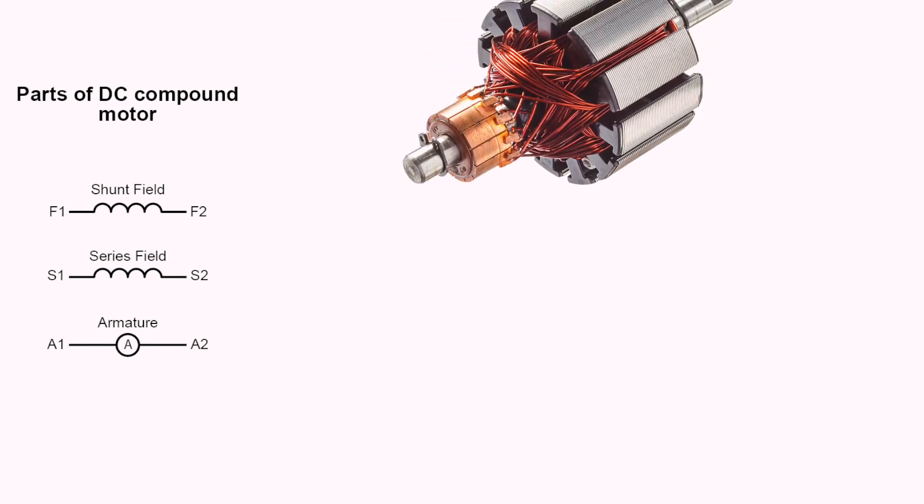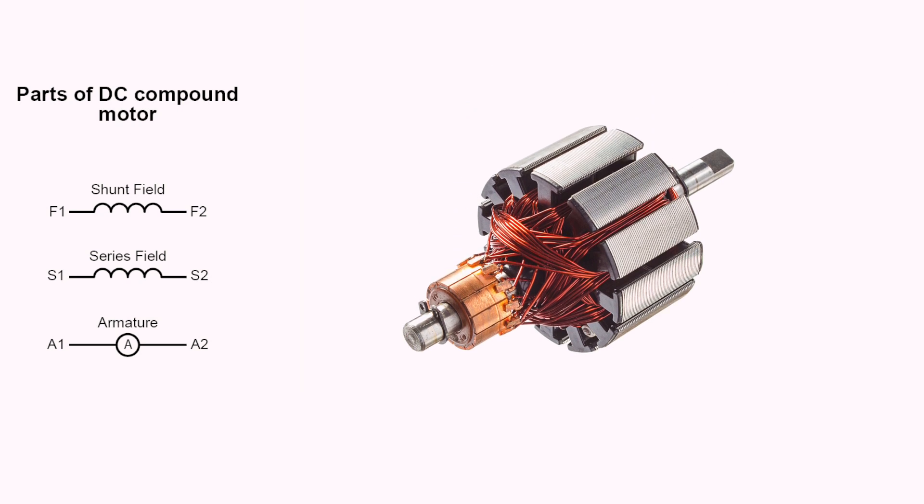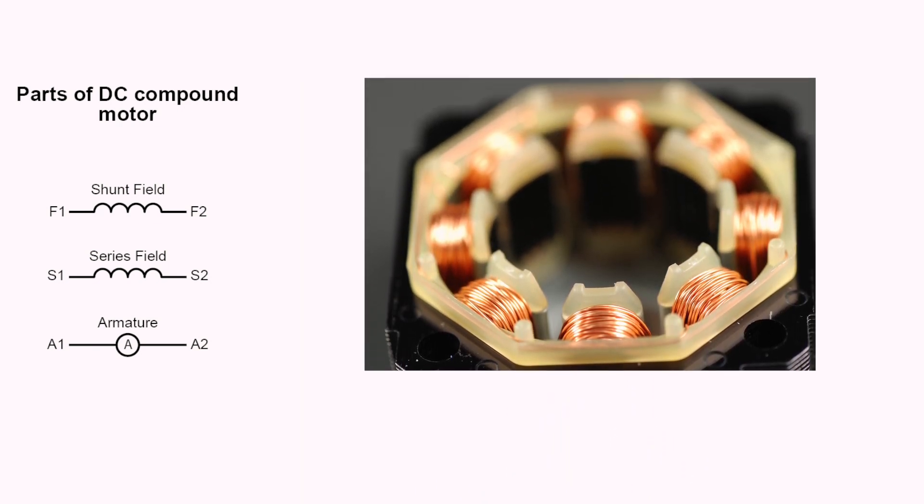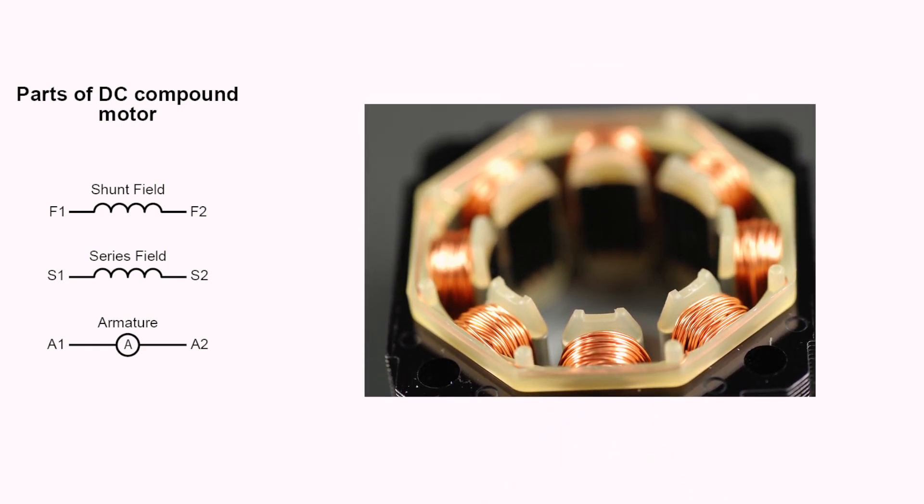These symbols that you see here are used to identify the basic parts of a DC compound motor. The rotating part of the motor is called the armature. The stationary part, which contains the series and shunt field winding, is called the stator. A1 and A2 are the armature leads. S1 and S2 are the series field leads. And F1 and F2 are the shunt field leads.